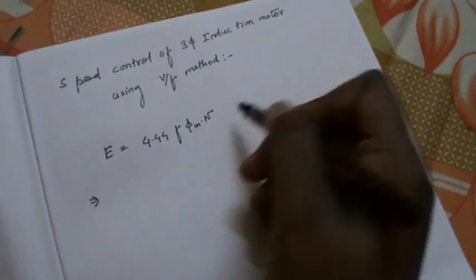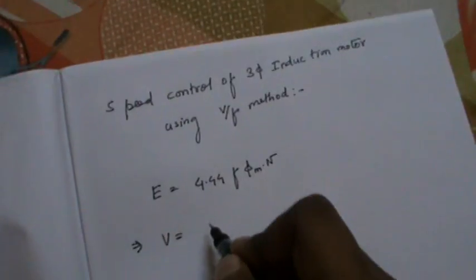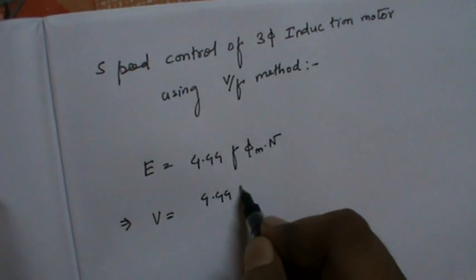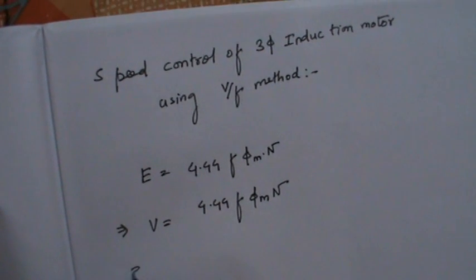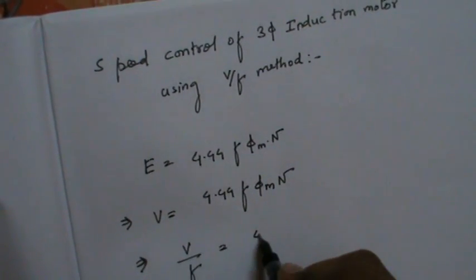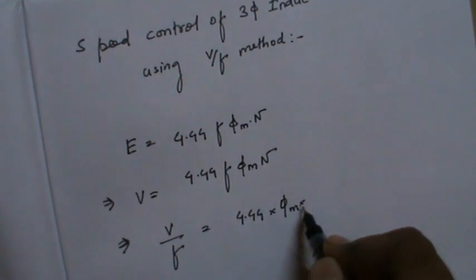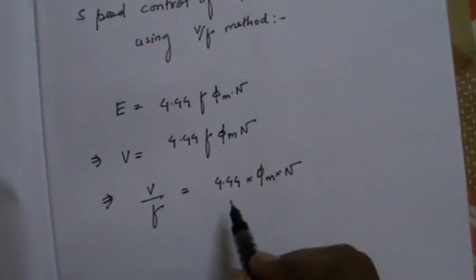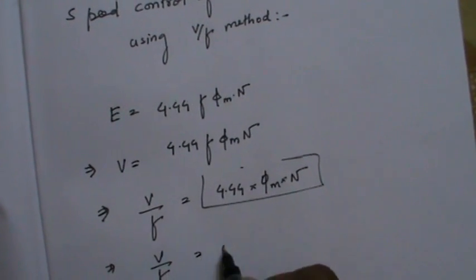So I can write this formula as V equal to 4.44 times φM times N. Here V is the applied voltage, so I can write V by F equal to 4.44 times φM times N. For an induction motor, this whole term is actually a constant, so we can write that V by F is equal to a constant.